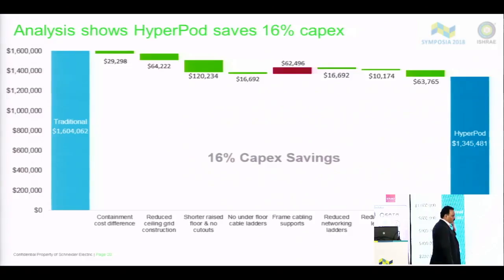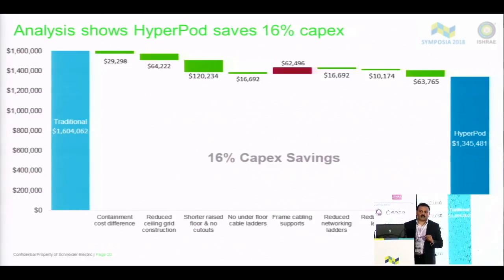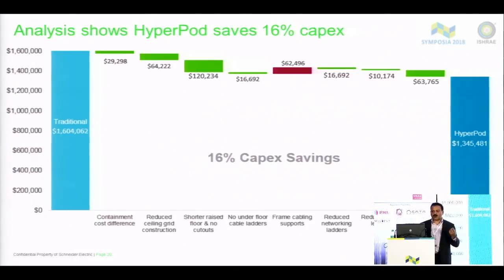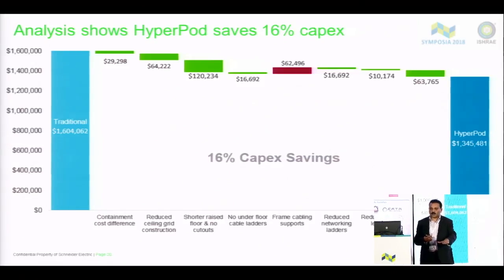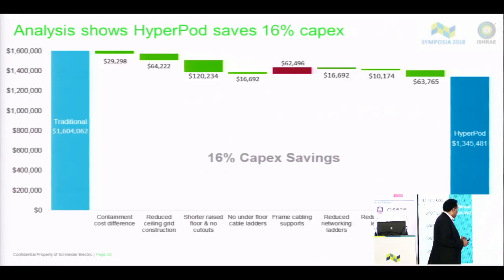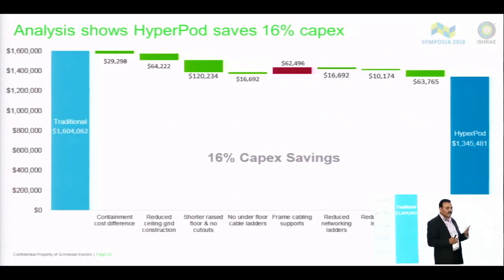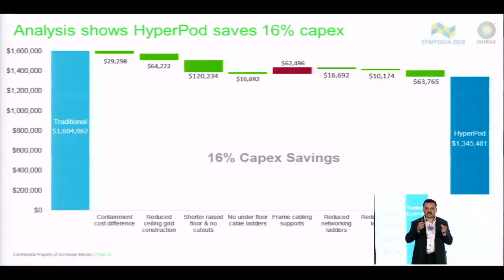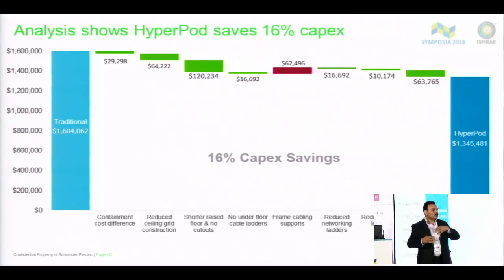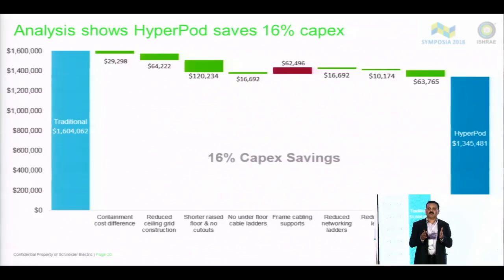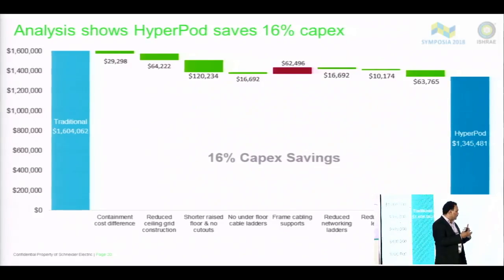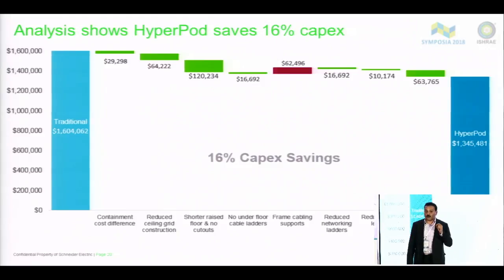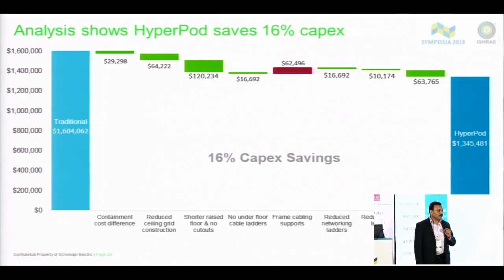And this is a waterfall flow of all the costs you incur in constructing a raised floor. Right from the containment cost difference, which is the basic one, you don't require a ceiling grid construction, and you can reduce the raised floor height. It's possible because it no longer has to carry multiple things inside. Frame cabling supports and networking ladders are reduced, and simple things like the power whips, the distribution cables from the distribution box to the servers, are reduced dramatically because you have a distribution unit mounted on the HyperPod itself. Our analysis shows close to 16% cost savings is possible by deploying the HyperPod solution, which is phenomenal.